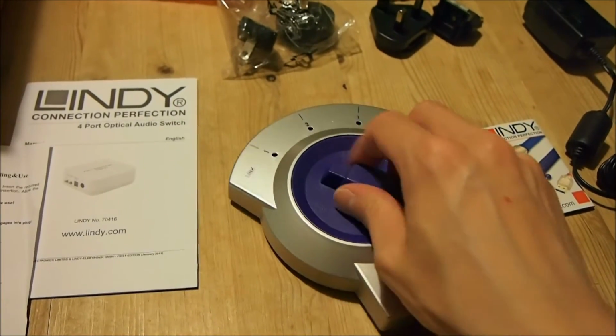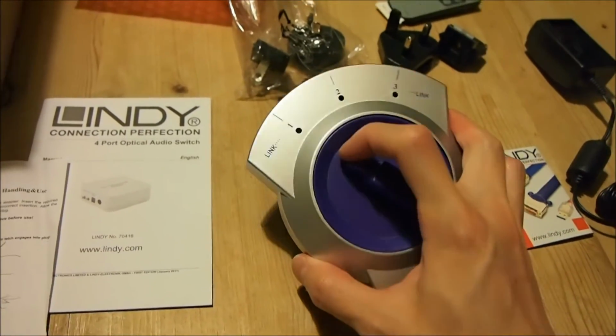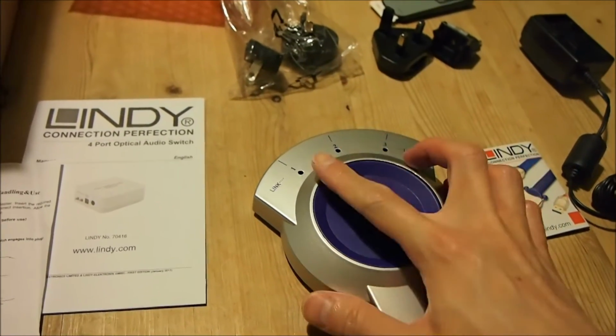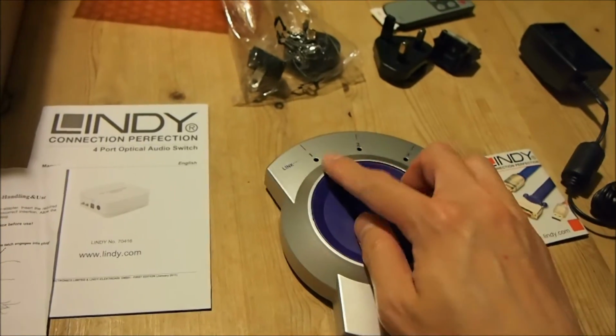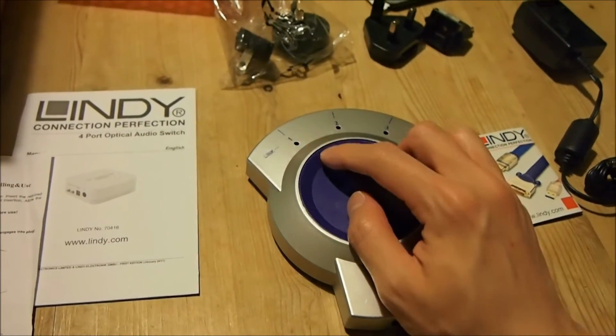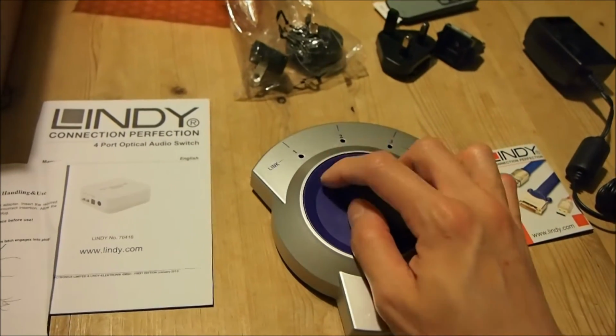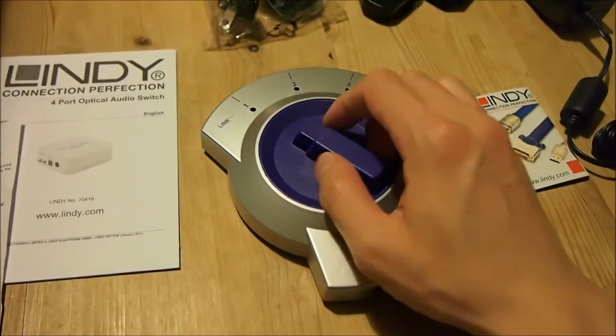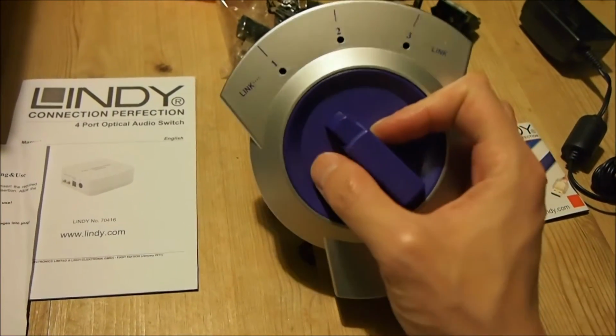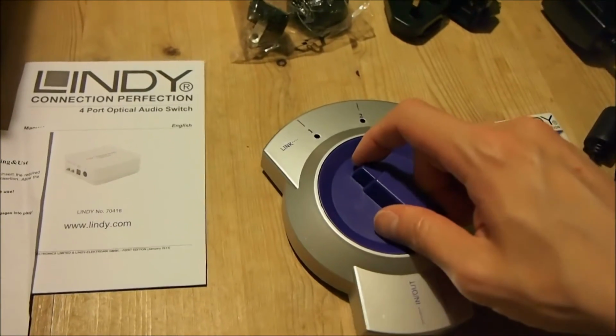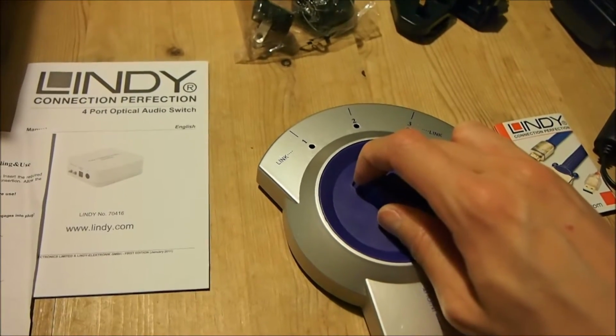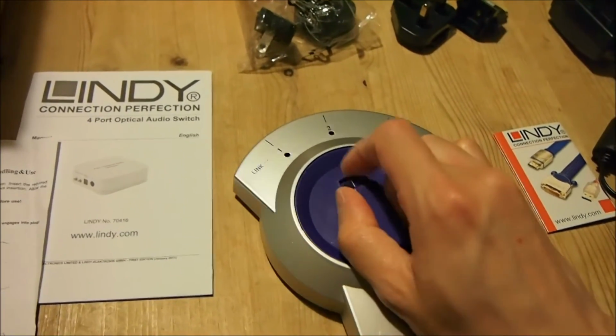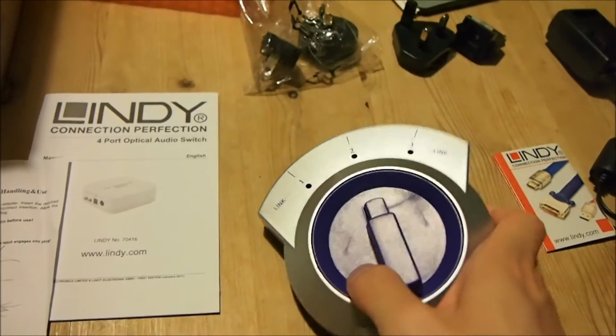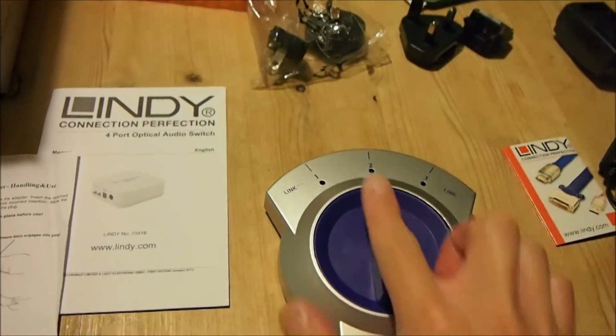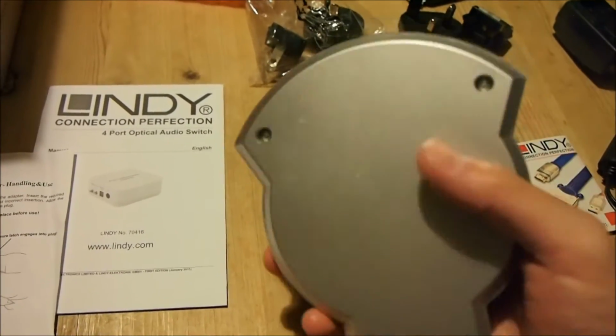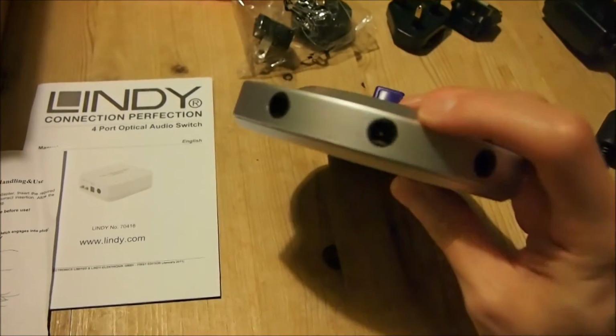Basically what this does is, when this button is depressed, it slides the other end of the fiber optic cable out from the port it's currently pointed to. At the moment it has port number 1 selected, so by depressing this button it retracts the cable from port 1, and then you move it to port number 2, it springs back and shoves the cable into port 2. As you can see, the cable is now in port 2 - you can see the white center core once again, and you can't see it on either of the other two ports.